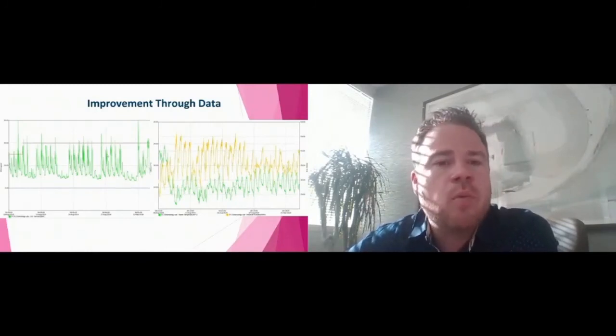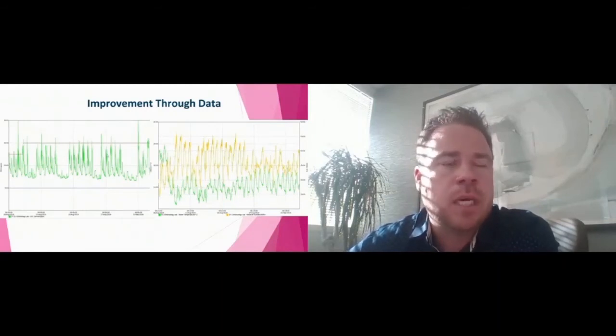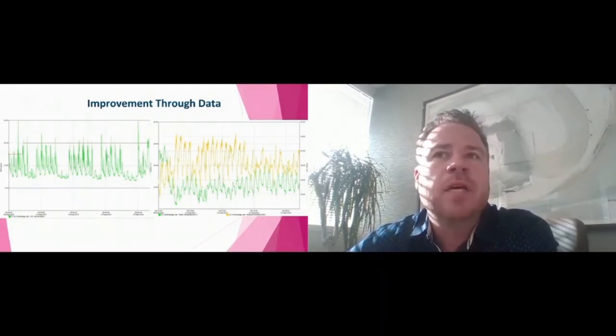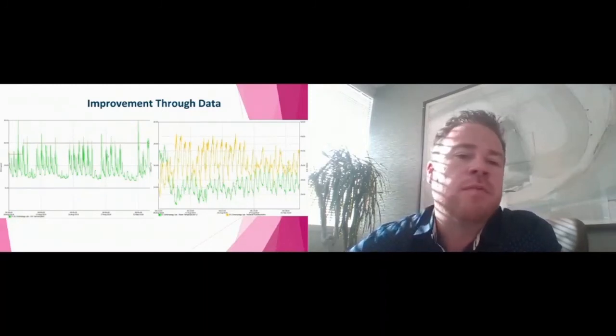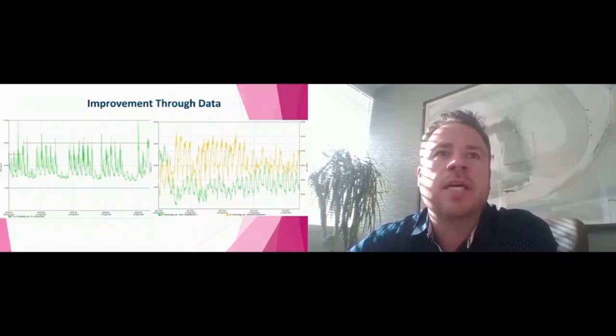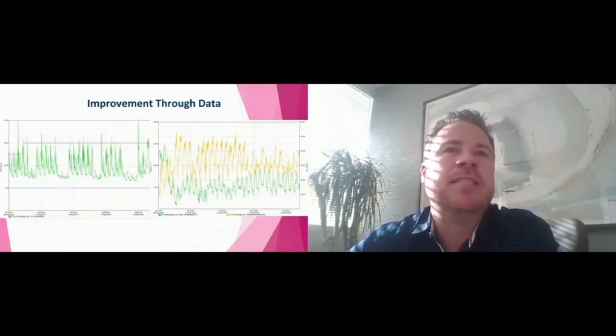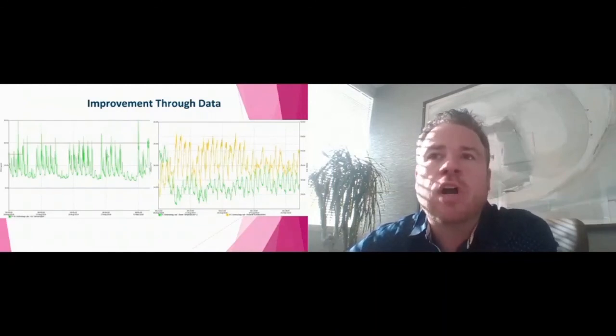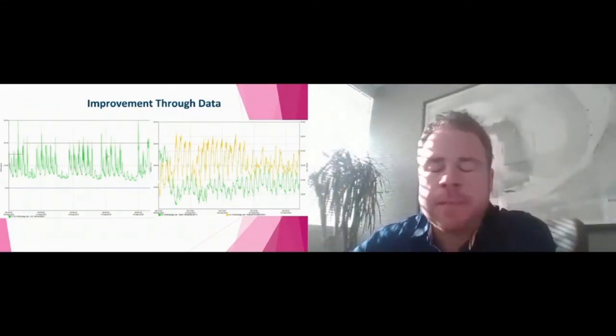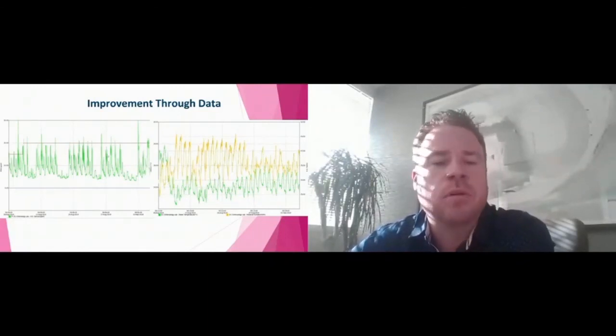It wasn't until we did this VOC monitoring and looked at VOCs throughout all of the labs that we realized we have air systems that do things that you would never have known. We didn't know that in Austin at midnight every single night, the AC unit for the building turns itself off and has a standard reset inside of it. Our VOCs jumped through the roof and then took time to autocorrect once that air system came back on. There was no way to know. It happens, I think, every night, like at 12:02 or something like that. And with that information, now we can go ahead and try to adjust. How do we want to do that?